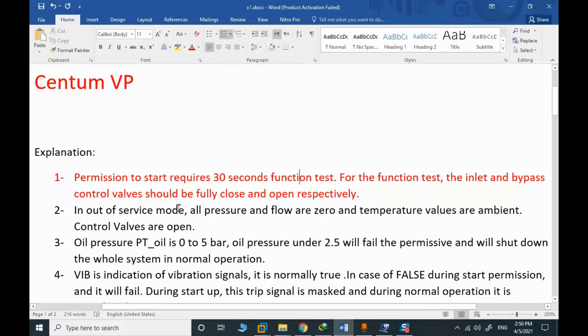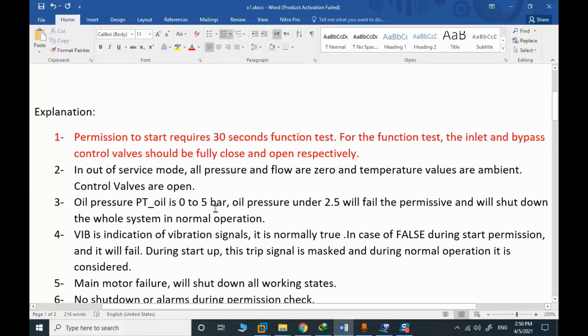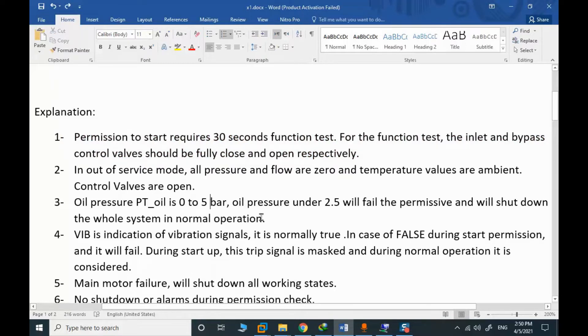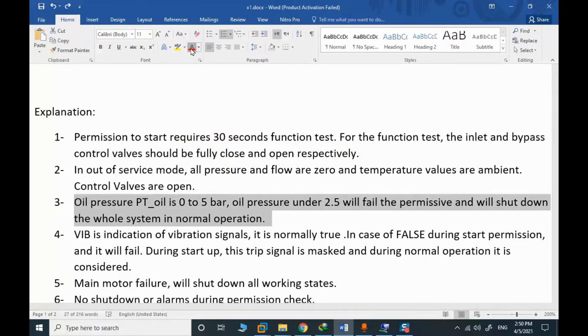In the out-of-service, as I mentioned, all pressure and flow are zero. Temperatures are ambient. Control valves are fully open. That is the out-of-service mode. Oil pressure is between zero to five bar. Oil pressure under 2.5 will fail the permissive and shut down.